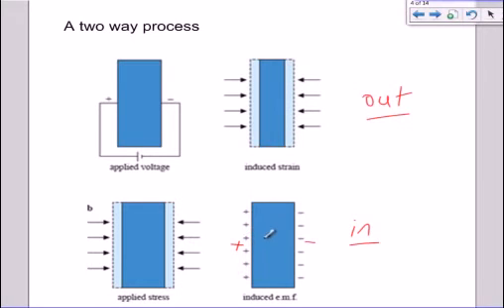So the positive and negative potentials here are induced by the vibration of the crystal. We can apply a voltage to make it vibrate. Or if it vibrates because of an incoming pulse, it will induce an alternating EMF across the sides, which we can then measure. And the induced EMF will depend on the amount of vibration.